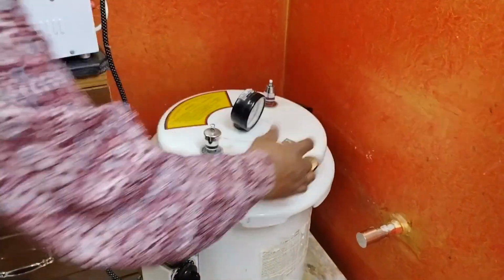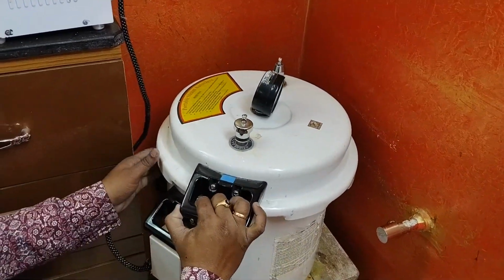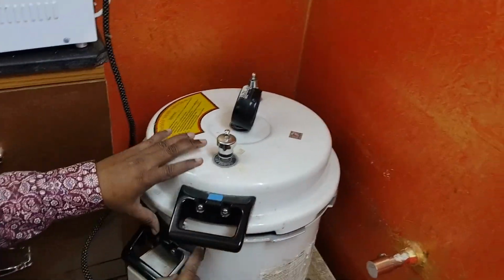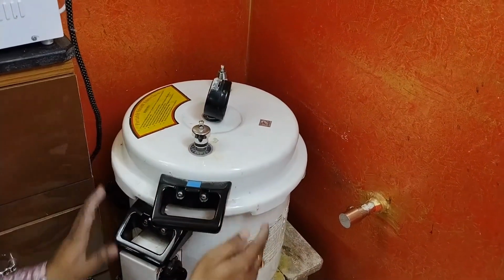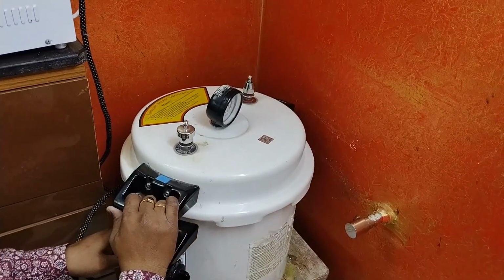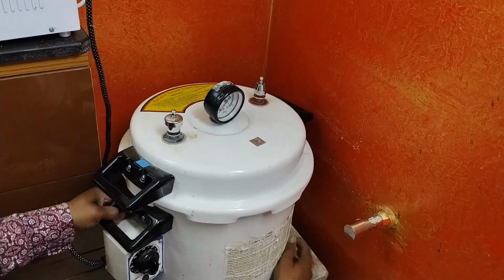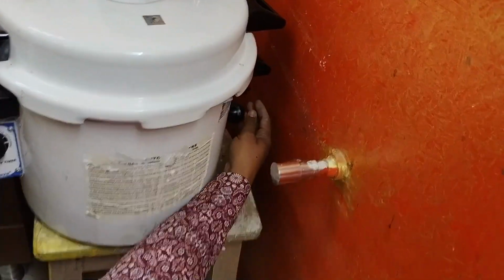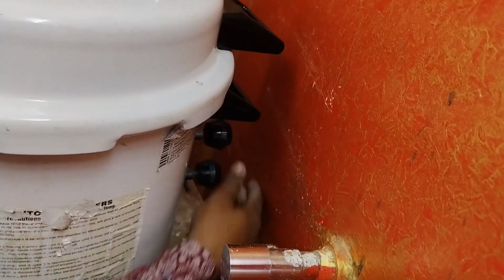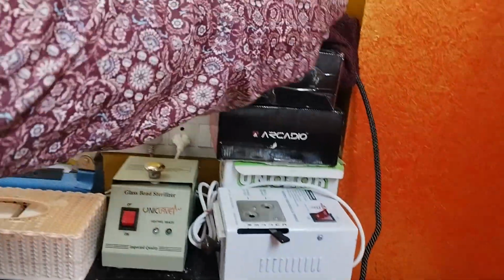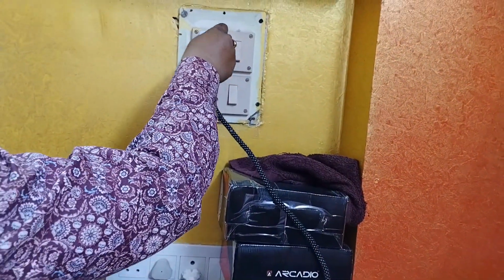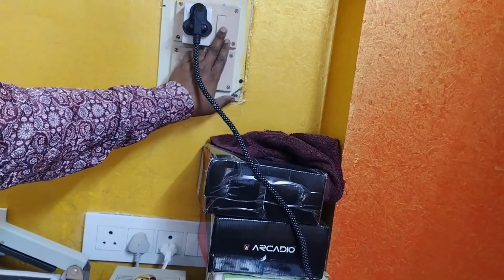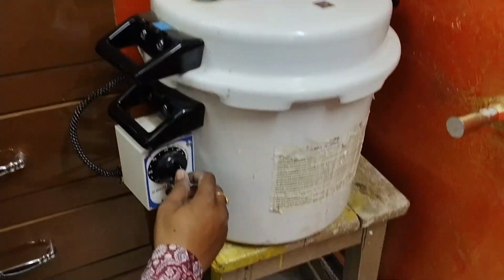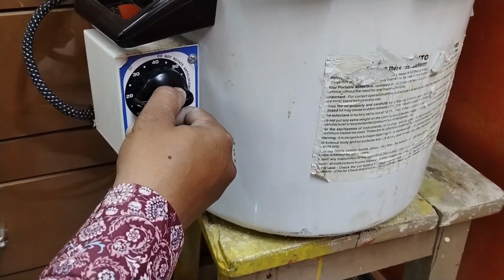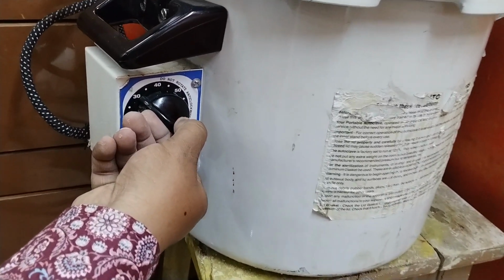This is the lid we are placing above it, and it should be interlocked. It should match this one. The point will be there, and you should rotate it, lock it, and see here the valve should be tight. Place the plug in the socket and switch on the autoclave. And this is the timer we are keeping for 30 minutes.